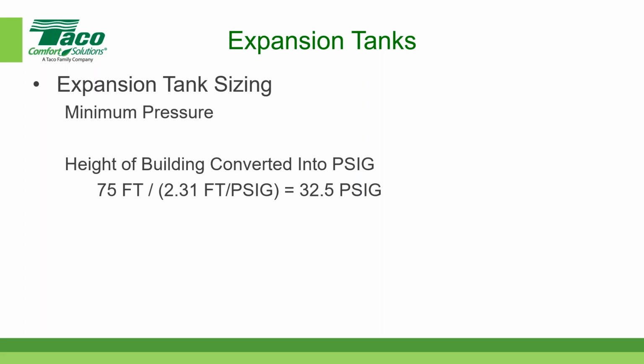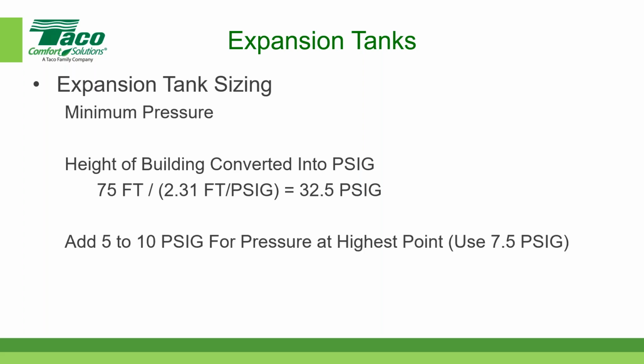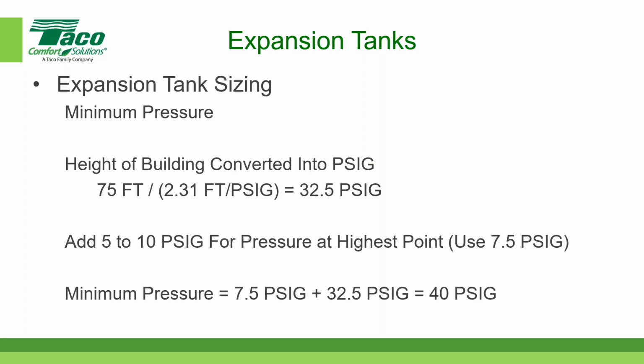Remember, at the top, in the little diagram, we said there was 0 pounds at the top. So now you have to increase the pressure in the system until, in our case, you get 7.5 at the top, which meant that you had 40 at the bottom. So in our case, we just said for 7.5, add that to 32.5, and that's the minimum pressure at the bottom, which is also equal to the pre-charge pressure. That's the pressure that you're going to add to the air side of the expansion tank, bringing the compressed air pressure up to 40 psig. And you do that before you connect the expansion tank to the system.